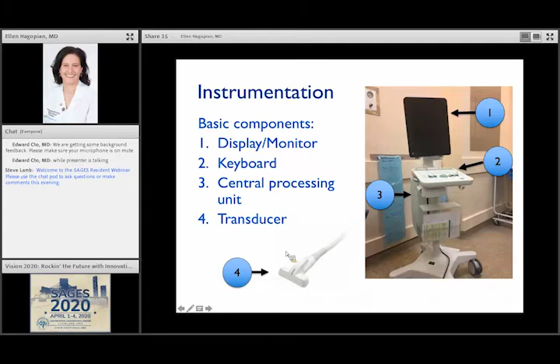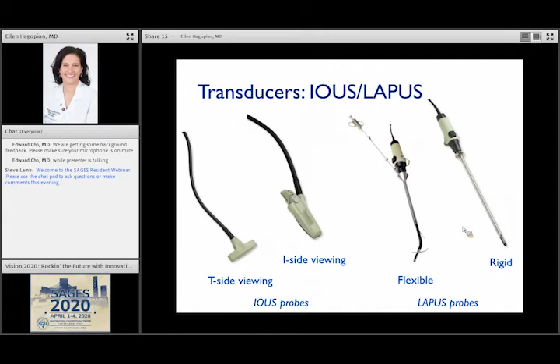For intraoperative ultrasound, we have the T side viewing probe, a T probe, which, as you notice, the ultrasound crystals are perpendicular to the shaft of the ultrasound cord, and that's why it's called a T. Or we have an I viewing, which is parallel. The ultrasound crystals are parallel to the shaft of the ultrasound cord. In laparoscopic ultrasound, we have flexible probes and we have rigid probes. In most cases, we use flexible probes for laparoscopic procedures.